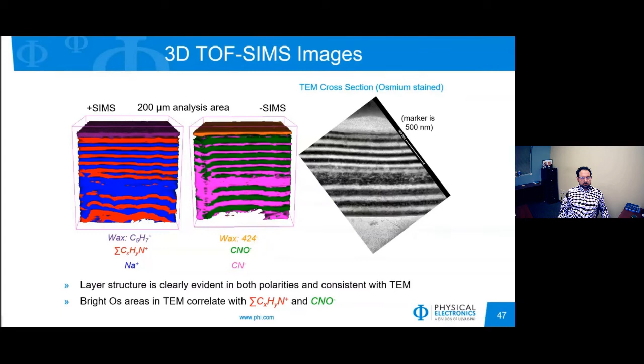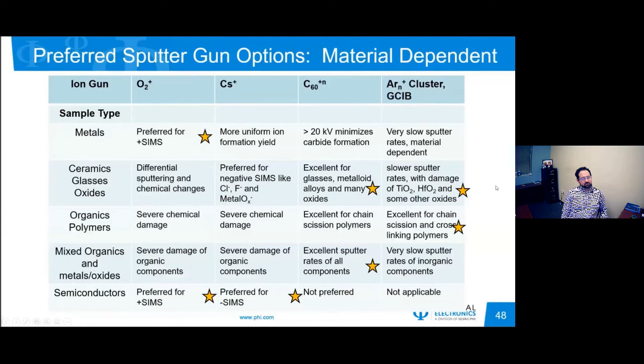So we've highlighted the different sputter gun options, what you can use to sputter your sample or to analyze your sample. And so there's some material dependence on the type of ion beam you want to use, so what kind of information you want to gain. Oxygen is primarily used for positive SIMS, enhancing electropositive species. Cesium can be used for enhancing negative species by orders of magnitude, as well as C60, which can be used, as we've shown here, with excellent sputter rates for organic and inorganic, so mixed materials. And then shown with the Damselfly example, you can use gas clusters to sputter through organic material very well. So you really want to know what kind of samples you have and what type of analysis beam or sputter beam you want to use to generate your information.